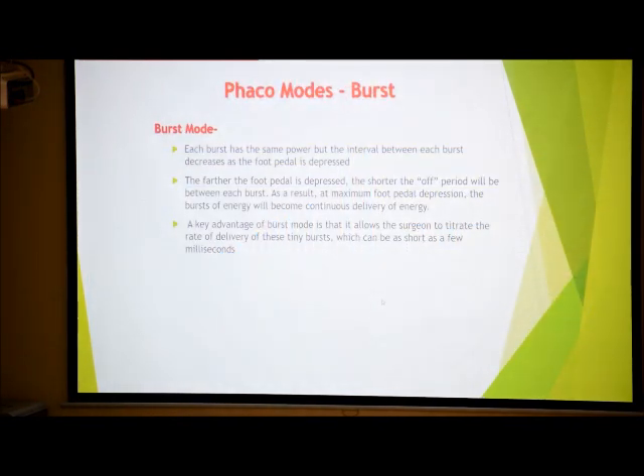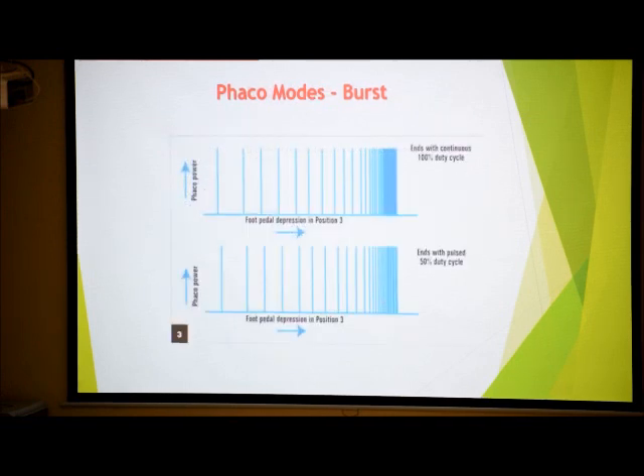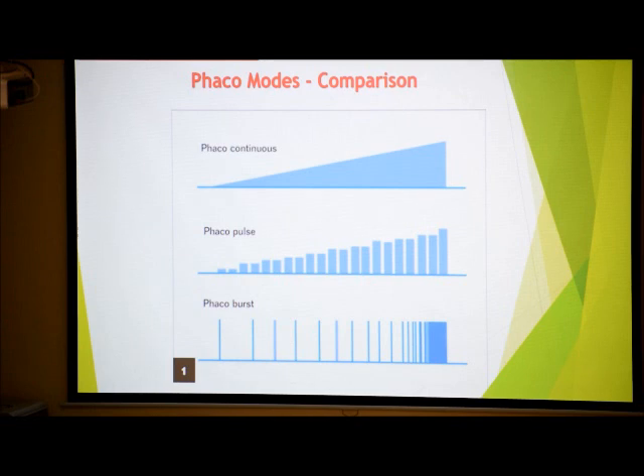Burst mode: the amplitude, or magnitude, of phaco power delivered at any time is constant, but the more we press the foot pedal, the more the frequency of delivery of this power increases. So at the highest point, when the foot pedal is at the extreme end, it is almost like continuous power. But from beginning to end, the magnitude of power is almost the same. So this is a comparison.